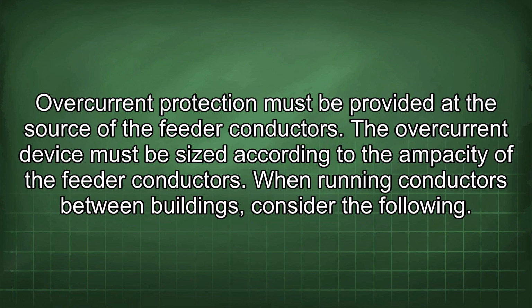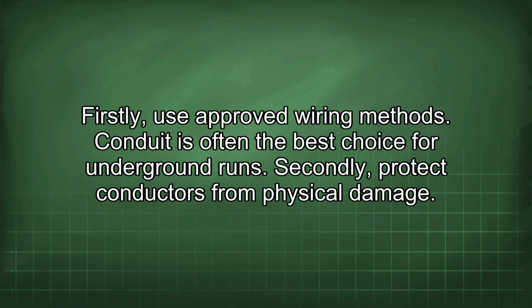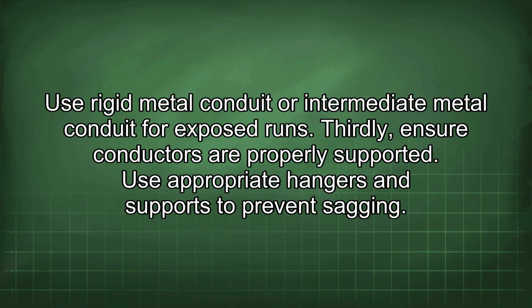When running conductors between buildings, consider the following. Firstly, use approved wiring methods. Conduit is often the best choice for underground runs. Secondly, protect conductors from physical damage. Use rigid metal conduit or intermediate metal conduit for exposed runs. Thirdly, ensure conductors are properly supported. Use appropriate hangers and supports to prevent sagging.